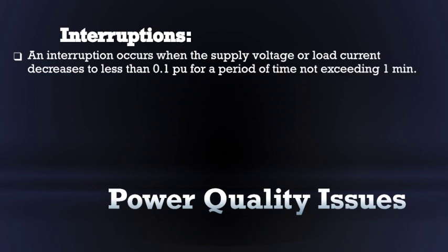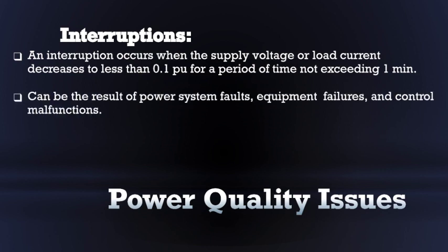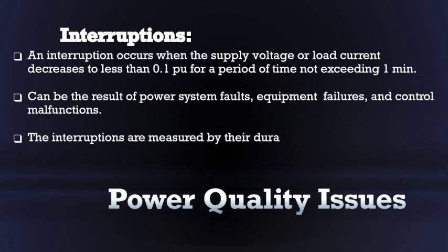An interruption occurs when supply voltage or load current decreases to less than 0.1 per unit for a period of time not exceeding 1 minute. Interruptions can be the result of power system faults, equipment failures and control malfunctions, and these are measured by their duration. The duration of an interruption due to a fault on the utility system is determined by the operating time of protective devices. Instantaneous reclosing generally will limit the interruption caused by a non-permanent fault to less than 30 cycles.